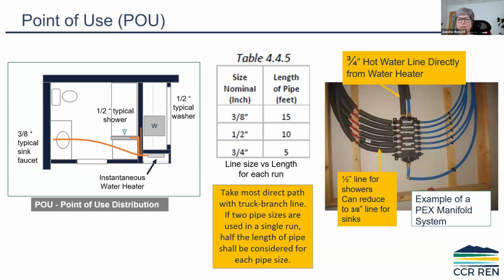Some of the projects we're starting to see use manifolds - this is a PEX manifold. Some people really don't recommend them because they're PEX, but you can get metal manifolds too. Part of what we try to get ahead of the curve on for clients and architects we consult with is using more point-of-use distribution and having more than one water heater in a project. If we have a really big sprawling house, we talk to them about using an under-sink electric heater at the wet bar since it's right there and not regulated in the same way the rest of the domestic hot water is.